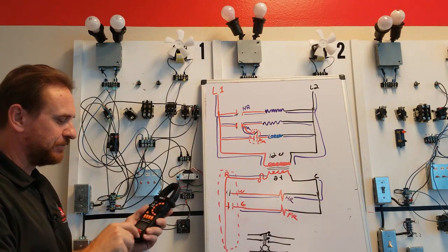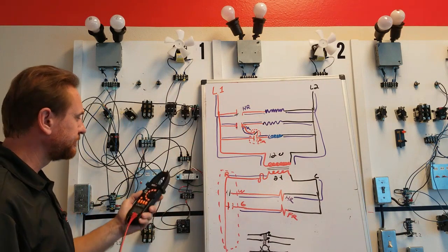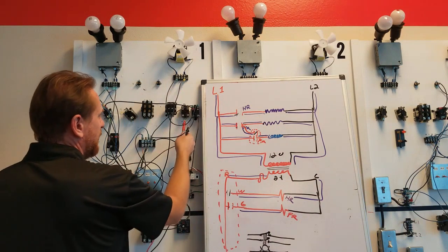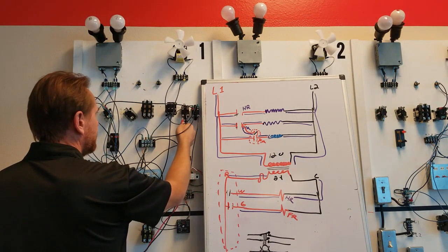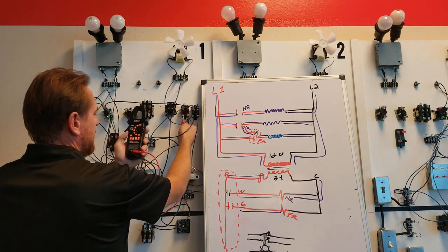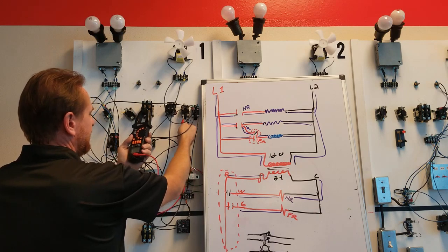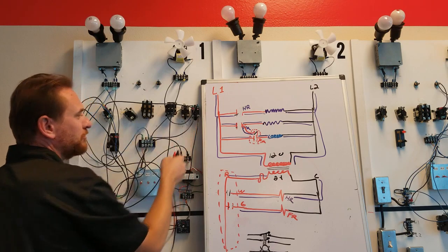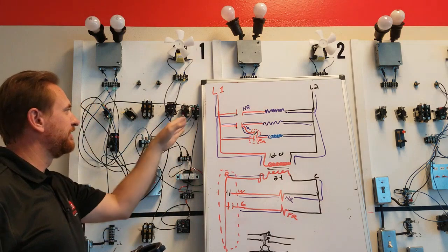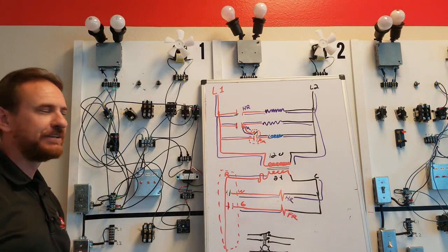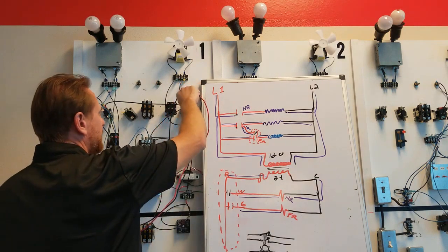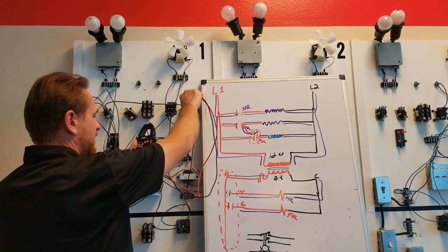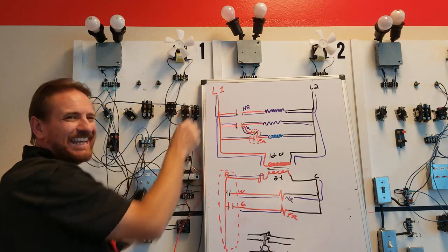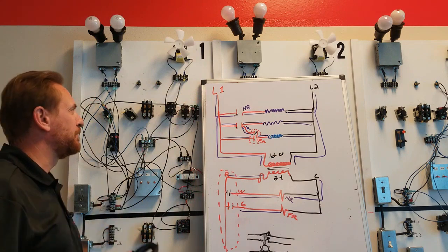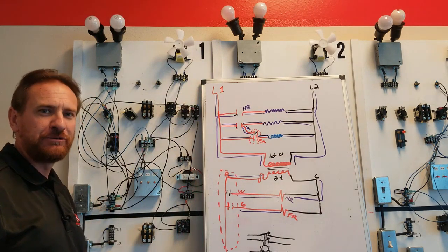So I'm going to take this meter, I'm going to turn it to ohms. And let's check these very bottom two terminals right here. We'll check this terminal, and we'll check this terminal. And I'm reading about, looks like 78 ohms of resistance. So if there is resistance, we know that it's going to be a load of some type. If I check these very top two terminals here, I end up with OL, infinite resistance, the most resistance you could possibly have. That means this switch is going to be open.